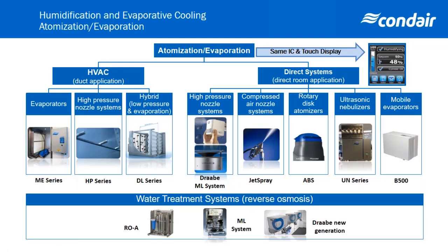So normally in healthcare and many office buildings, we're on the left-hand side here in the HVAC. So we're evaporating with the media system or spraying water into the air with high pressure or combining the two into one nice technology that allows for less duct space. And then, of course, we can also put water directly into the air in an office building in the space above people's heads. And this is actually becoming quite popular. It is very energy efficient and easy to retrofit. So that would be the systems here, the high pressure nozzle systems in the middle.